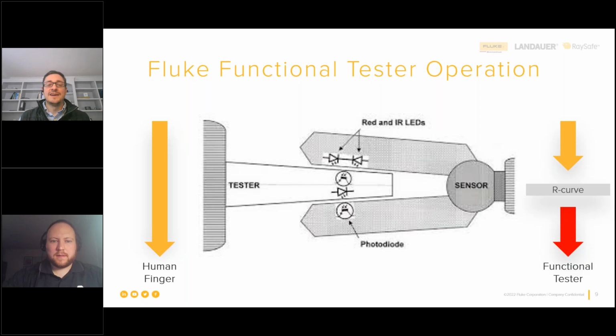And as the monitor shines light onto the top of the finger of the tester, red and infrared light, both in succession, the tester will measure the amount of light, will decide whether it's red or infrared, will calculate how much of that light should be shining through the other side of the finger, right, to say simulate 80%. And then it turns its own LED on the bottom so that it looks like it's shining through the finger. So that's kind of how the whole thing operates. In the background, it's also running heartbeat pulses, right, to approximate the shape of an arterial pulse. So that varies according to the current amplitude of the pulse. So it's not just a finger simulator, right? It really does a lot more.